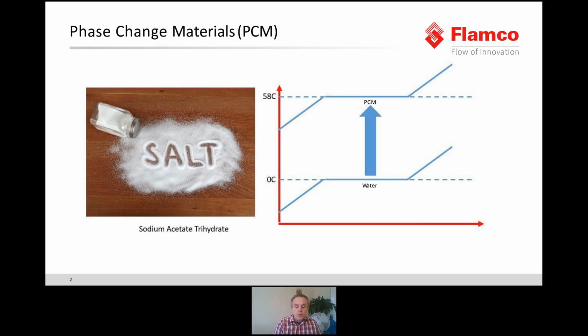So when a PCM cools, it releases a huge amount of energy in the form of latent heat at a constant temperature, which is 58 degrees C, which is then converted into warm tap water or space heating. The phase transition ensures an extremely high energy density. So key user requirements nowadays are high power charge and discharge for rapid recovery and on-demand high flow rate for hot water users. So it's really important that the PCM can be rapidly charged inside the heat battery and equally heat quickly extracted.